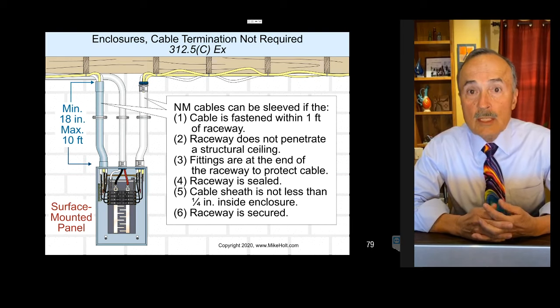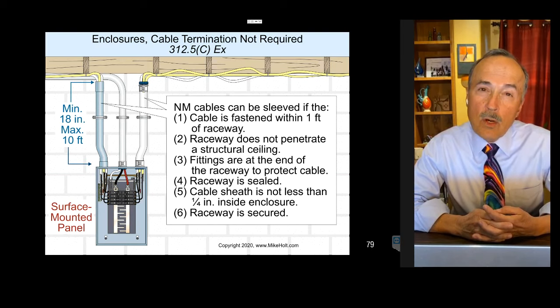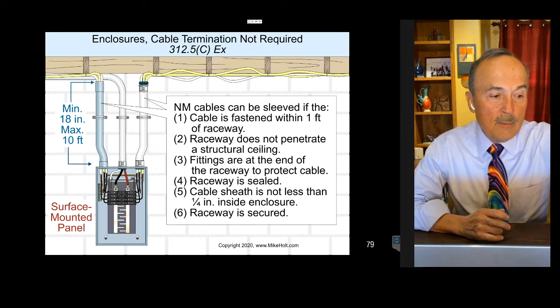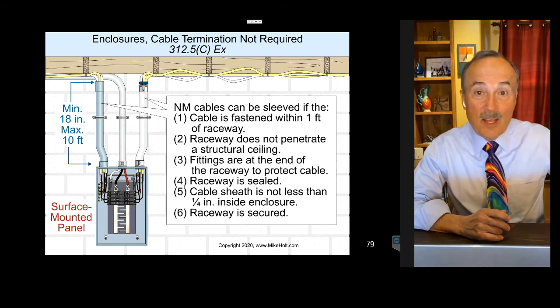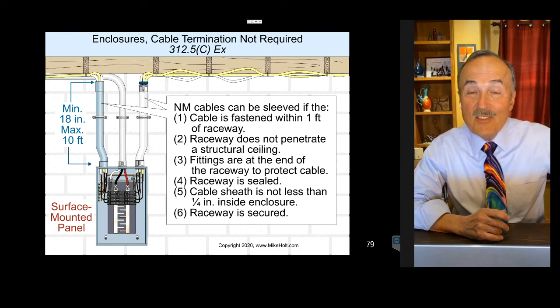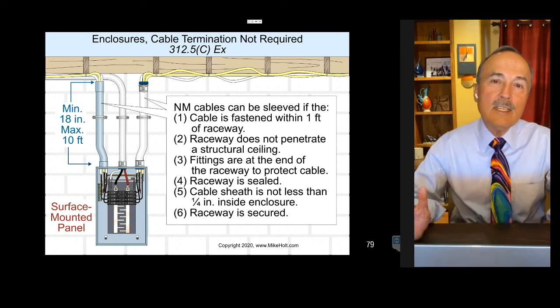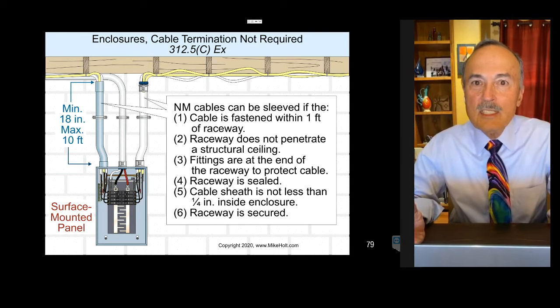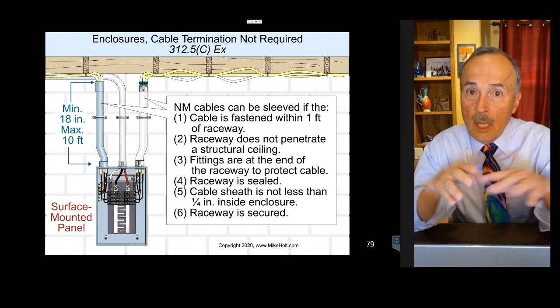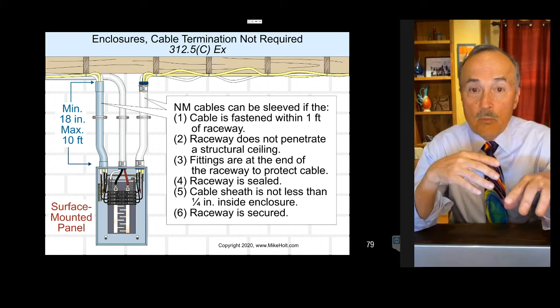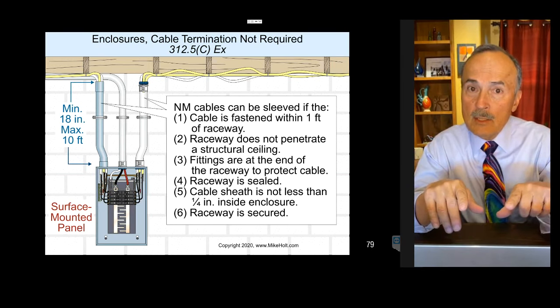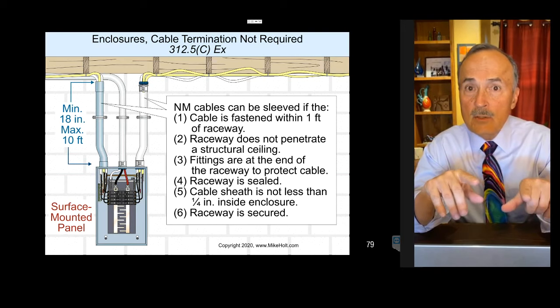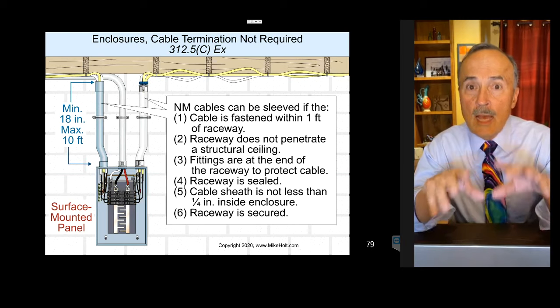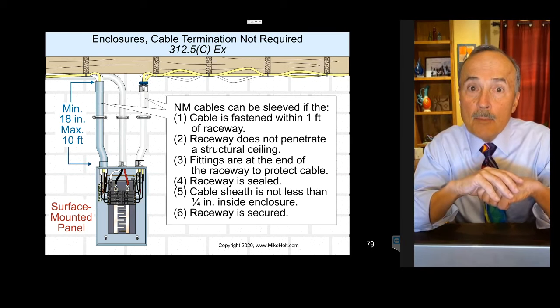Great. Look at this enclosure. It's surface-mounted. Oh, actually, there is a point there. So we need to make a point that this is required to be a surface-mounted enclosure. Well, how many times are you going to have Romex run on a surface-mounted enclosure and you're going to sleeve it up? Oh, but if you put it inside the walls and you put drywall on it, the electrons know the difference, and you can't do that. Yeah, listen, sometimes the code doesn't make sense, but you have to remember something. A lot of people hate Romex. And so if this is the way to stick it to Romex, though it doesn't make any sense, they don't care. I'll make a public input to change this to say, look, guys, come on. What does it matter if it's surface mounted or if it's concealed? It's the same thing.